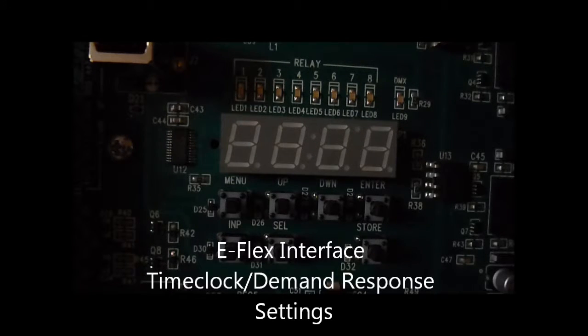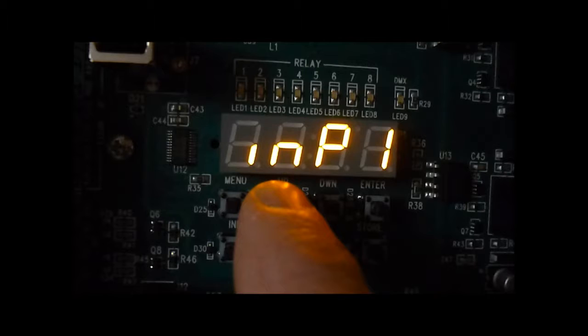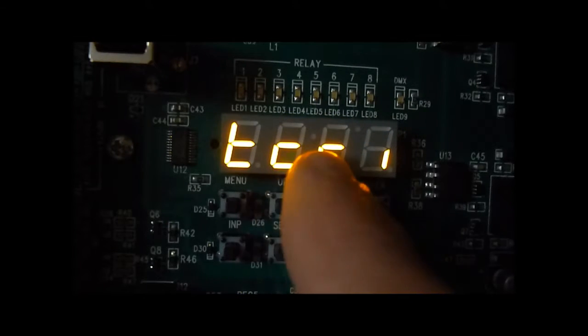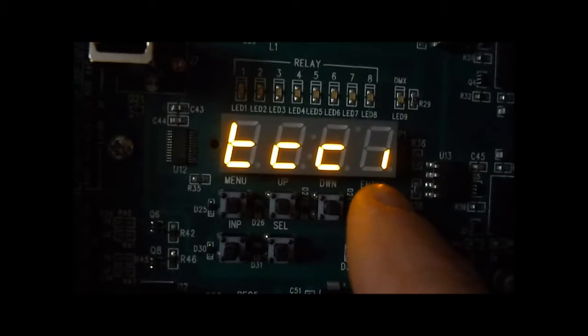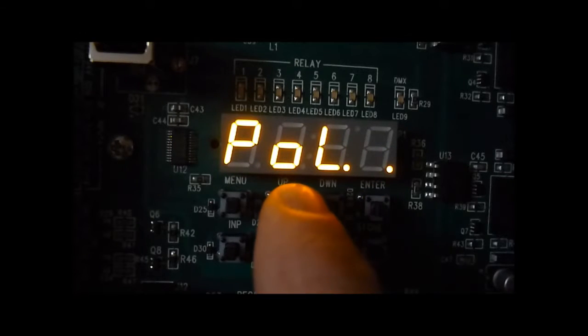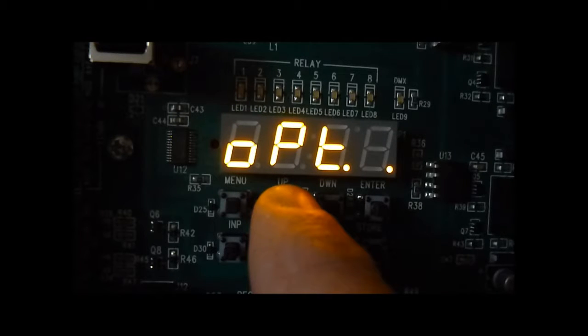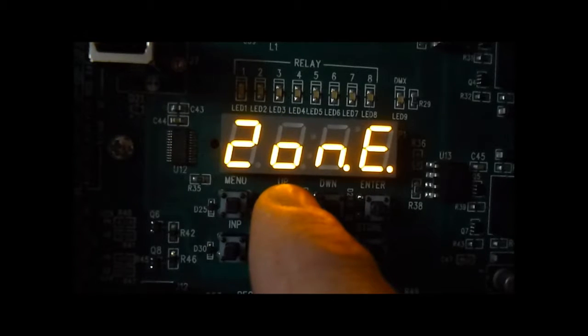In this video, we'll show you how to configure the time clock input on the eFlex relay panel. Press Menu, scroll up twice, time clock, contact closure input, press Enter. There's several menu item selections: polarity, mode of operation, zone assignment, response preset for certain modes of operation, and demand response settings when the operating mode is set for demand response.